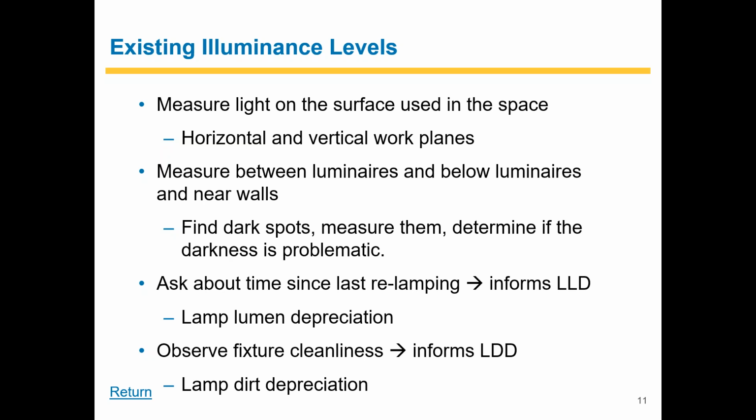The same thing applies with fixture cleanliness. When a customer has generally been skipping out on their lighting maintenance, they're also not getting up there to wipe away dirt, dust bunnies, and all sorts of debris that could otherwise obscure or reduce the effectiveness of the optical system. So you want to make sure that you're including lamp dirt depreciation in your analysis. As a general rule of thumb, in most interior environments, where it's not an iron foundry or a gas station with a lot of particulate matter, after about 8 years of no cleaning, you're going to have about 6 to 8% light loss just from dirt.